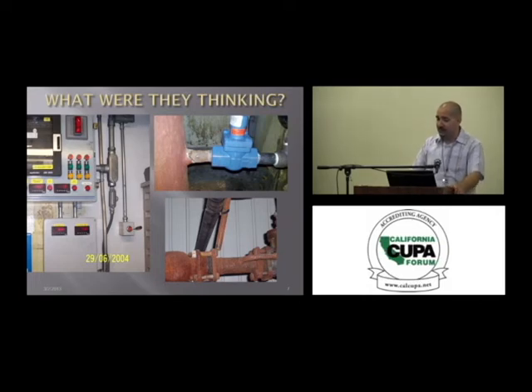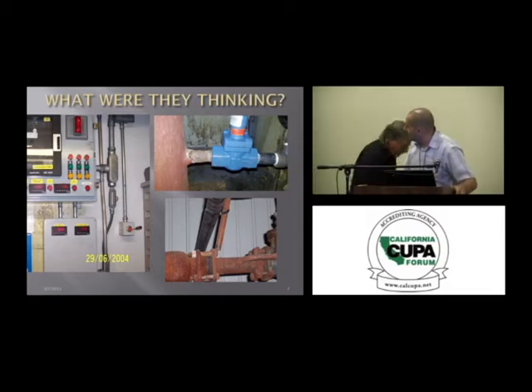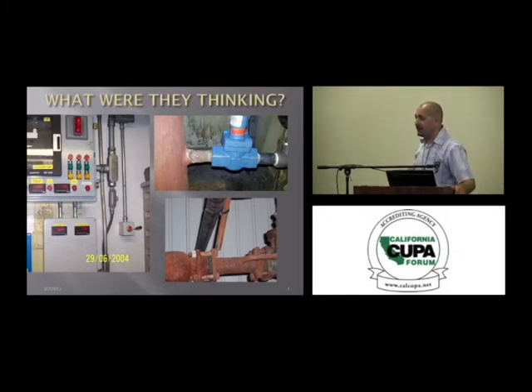You can see the top right-hand corner. That valve there, it's a brand new valve. I was doing an MI inspection at this facility, and as I was walking up, the refrigeration contractor that was there, they were replacing this valve. And you can see to the right side of that valve, they got new nipple piping, new fittings, but that's the drop leg of an accumulator inside the bunker. So that's full of ammonia, had some oil in it as well. But you can see the corrosion on that pipe nipple there. I'm surprised that nipple did not break as they're removing the pipe and putting that pipe back on there. And they didn't do anything about changing out that nipple, so now the system's in with pressure, and you got a very corroded nipple.